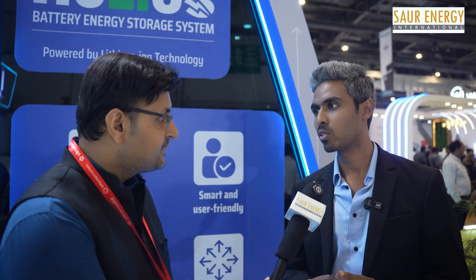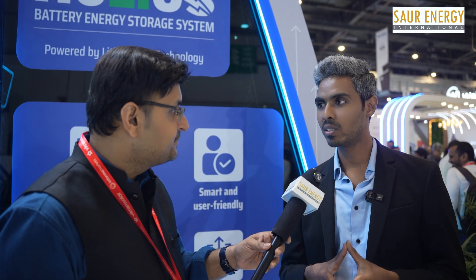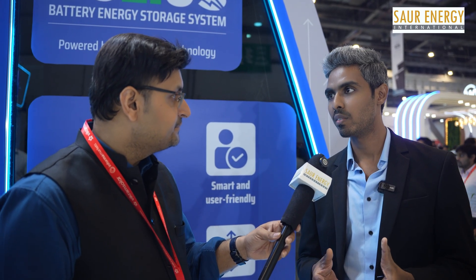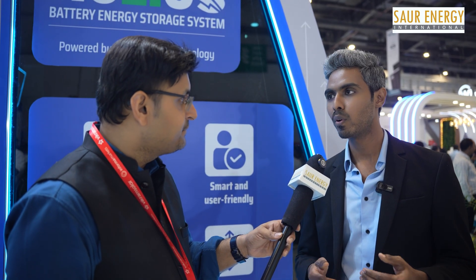Lithium-ion batteries have a different set of advantages, which is very new for the Indian market. Today the price is 2x that of lead acid batteries. However, the cycle life, the total cost of ownership (TCO), and the faster charge rate are advantages of lithium. It's ultimately a consumer choice based on size, weight, volume, cycle life, or preference for a proven standard technology. Consumers can choose lead versus lithium accordingly. The shift to lithium really happens at higher kilowatts — 30 kilowatt and above — where you can't string so many lead acid batteries.